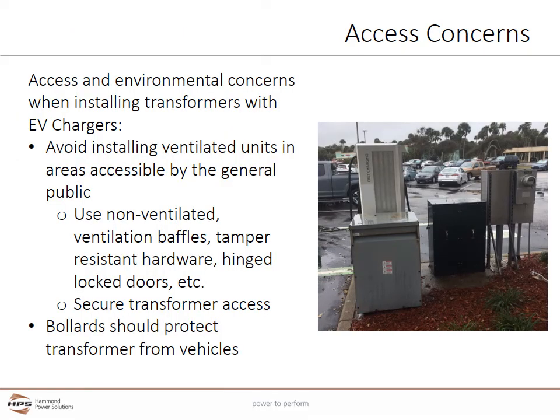There are access and environmental concerns when installing transformers with EV chargers, especially in exterior locations. Avoid installing ventilated units in areas accessible to the general public. Use non-ventilated units, ventilation baffles, tamper-resistant hardware, hinged locked doors, and other methods to limit access to energized parts. Preferably, install the transformer in a secure area. Bollards should protect the transformer from vehicle contact, even from vehicles as small as golf carts and bicycles.